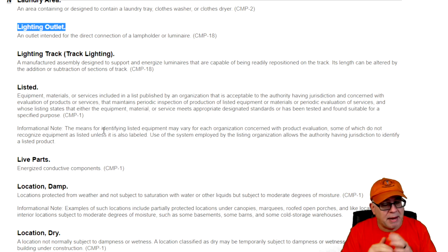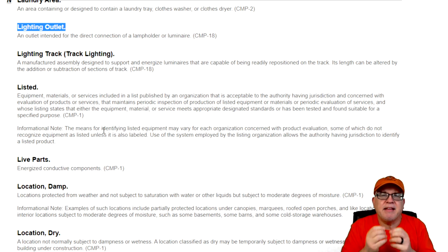There's very limited applications where you can use that. Obviously not in closed closets, it has to be totally enclosed. But at any rate, a luminaire is a full assembly. Okay, and we'll see that definition here shortly. But a lamp holder is holding the lamp, but the lamp is the bulb itself, I guess you should say. And you're making that direct connection to it inside that outlet box.